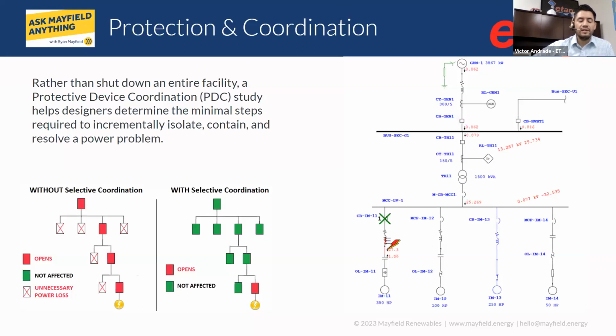and you as the engineer or the ETAP operator can actually place a fault anywhere in the system, right? So you can select, well, I want to fault the line side of an inverter, like the AC side of the inverter, the DC side. I want to fault right at a panel. I want to fault my main substation, and the software will go through the sequence of operations. So it's a very intuitive, very easy way to prove either to your customer or to the rest of your design team what would be the impact of a fault in the system, how well it would be isolated.